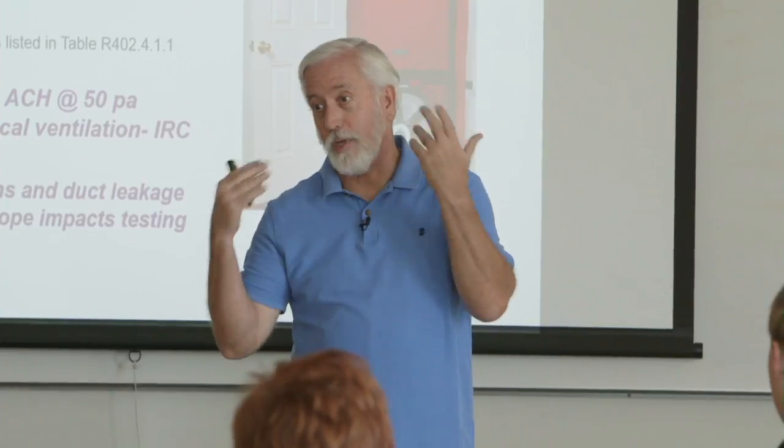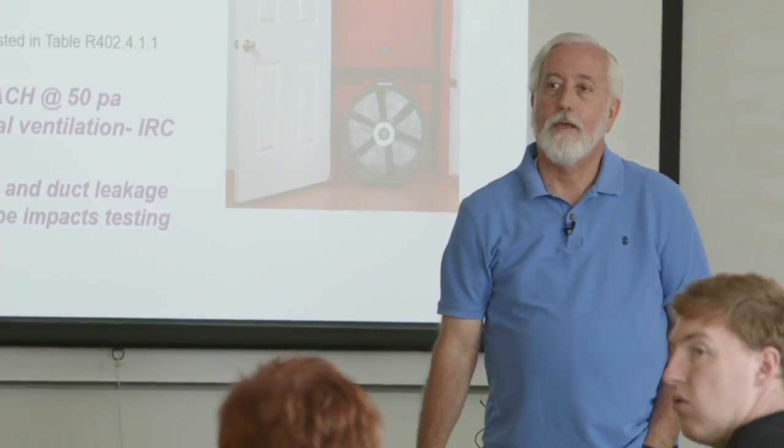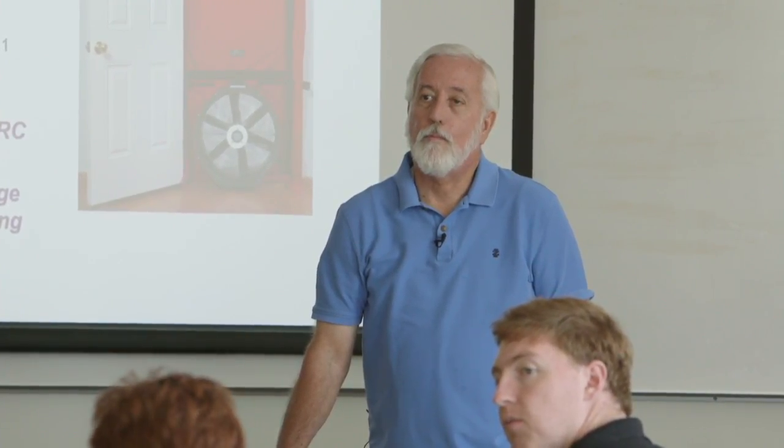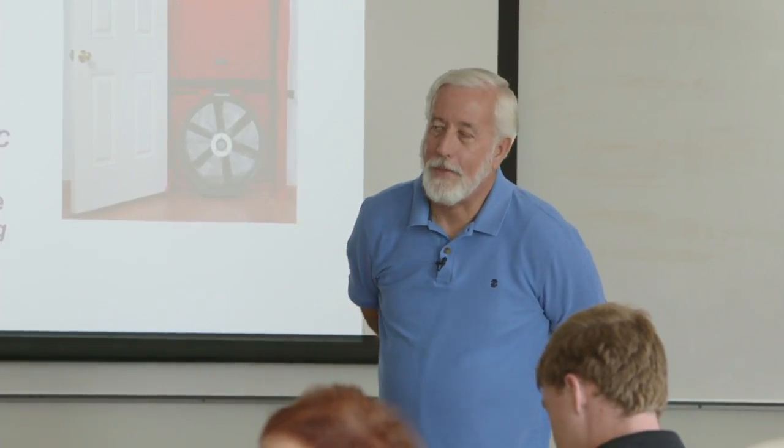We really solve those by just going direct vent. Hey, Brent, I should emphasize that the fan system has to be designed very carefully, because typically a 100 CFM fan maybe gets 50 because of the ducts. So don't underestimate, don't put in a 100 CFM fan and expect to get 100.